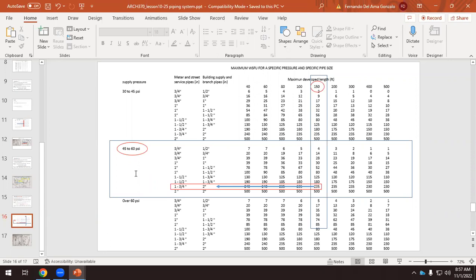So when you have designed this building, now the building that you are working with in Revit, well, that's the second time. This is the first time you're doing this. The second time will be on Friday with your Revit file. But every time that you are designing a 2-floor building with 4 restrooms, male and female, with 5 toilets or sinks, something like that, what's the pipe that comes from the city supply? 2 inches.